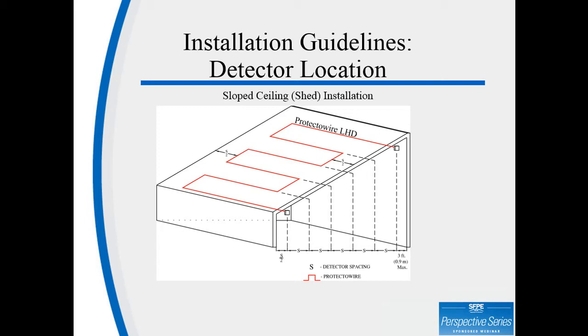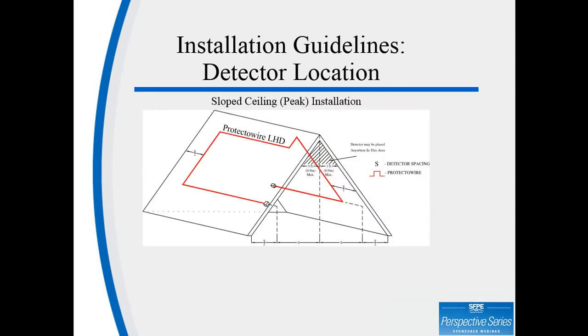LHD detector location on slope ceilings or shed installations. In areas having a sloped or peaked ceiling, at least one line of Protectowire, or LHD, must be located at or within 3 feet, 0.9 meters, measured horizontally from the peak, but not closer than 4 inches, 10 centimeters, vertically to the peak. The spacing of additional runs of Protectowire, if any, should be based on the horizontal distance projected down from the ceiling in accordance with the type of ceiling construction.